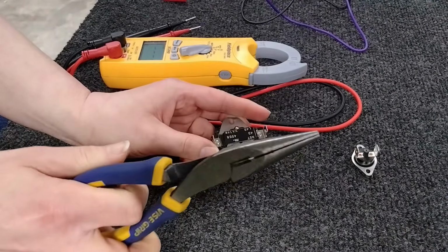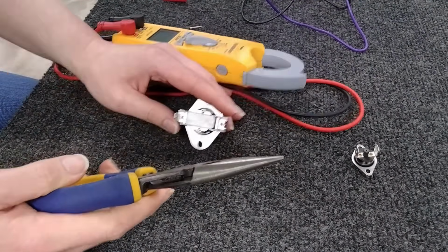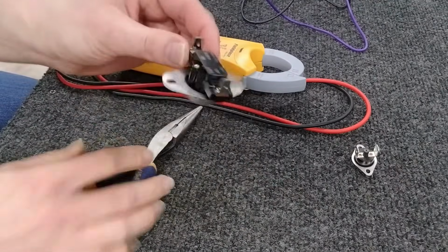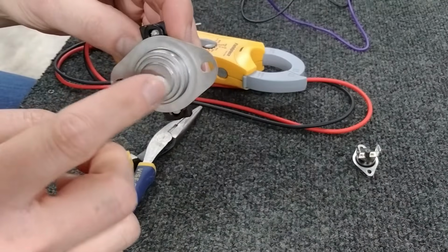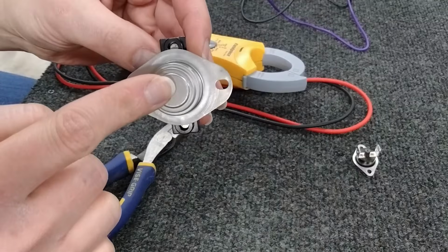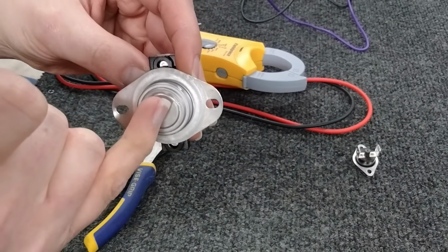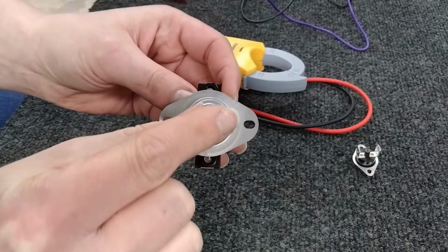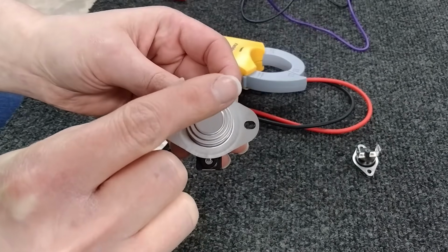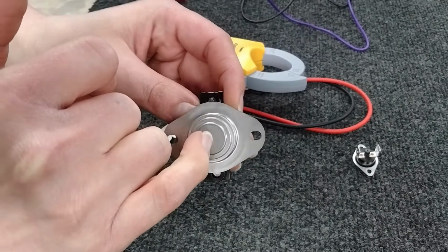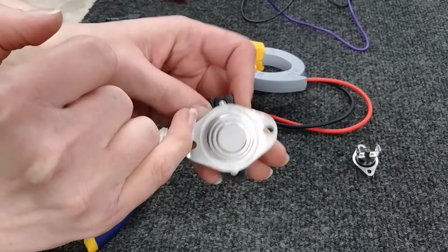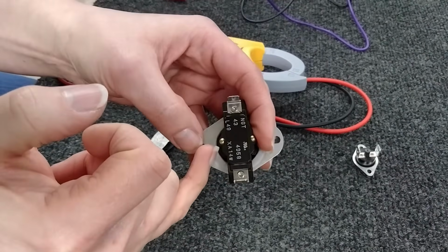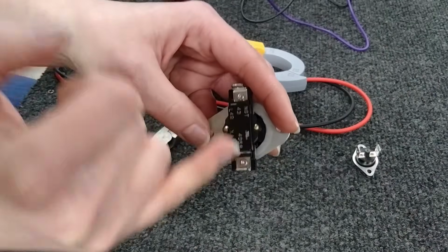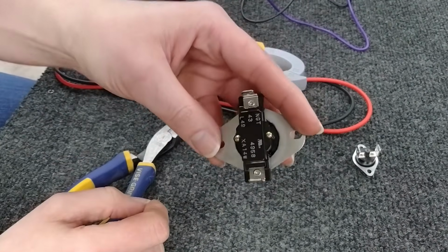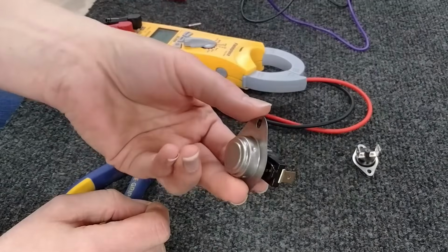It's good to have something like this to hold it out so you don't burn yourself. Basically, what's in here is a thermal disc with a pin. When this gets overheated, that disc pops up, kind of bubbles. That causes the pin to go up through here, which opens the circuit, no longer allowing your electricity to come through. And it's not going to reset until it cools down.